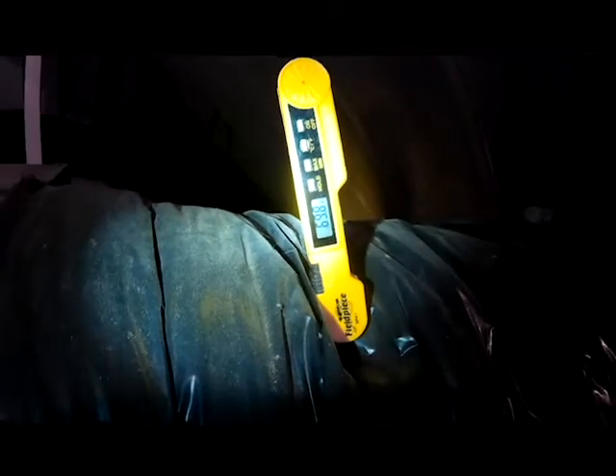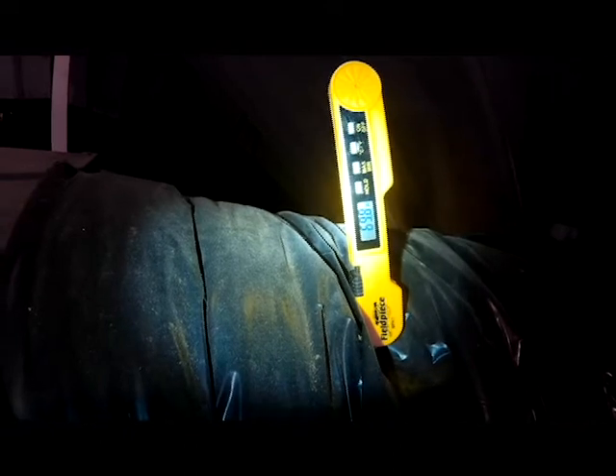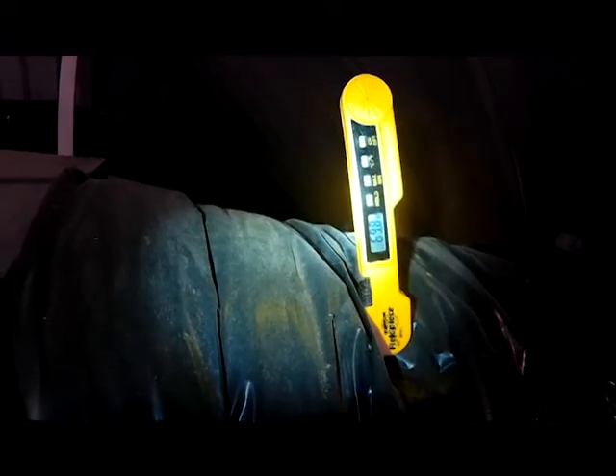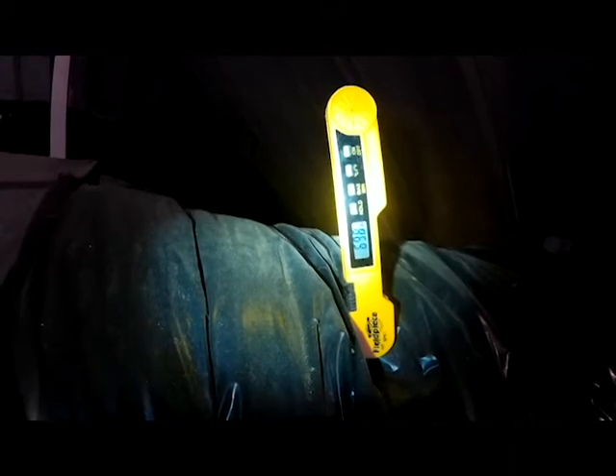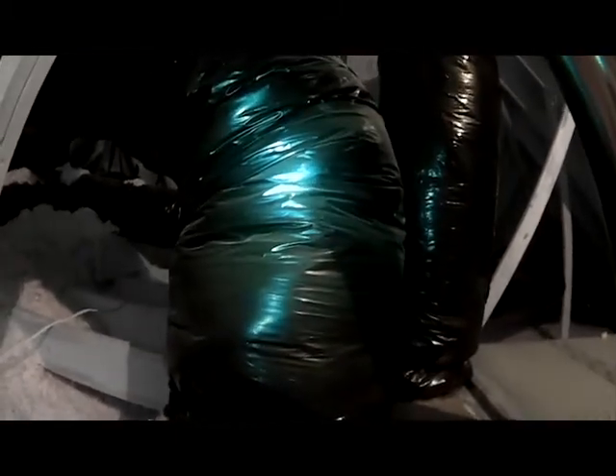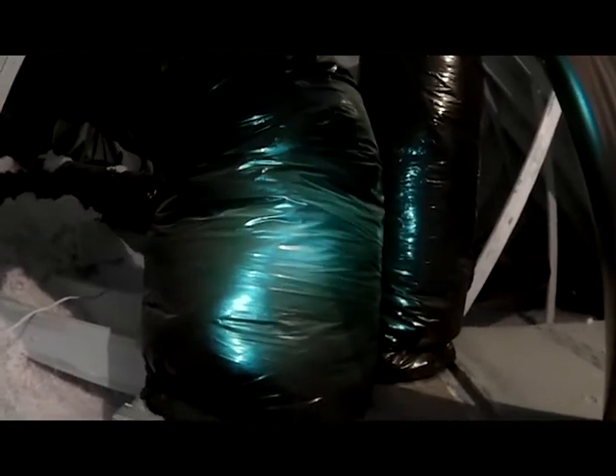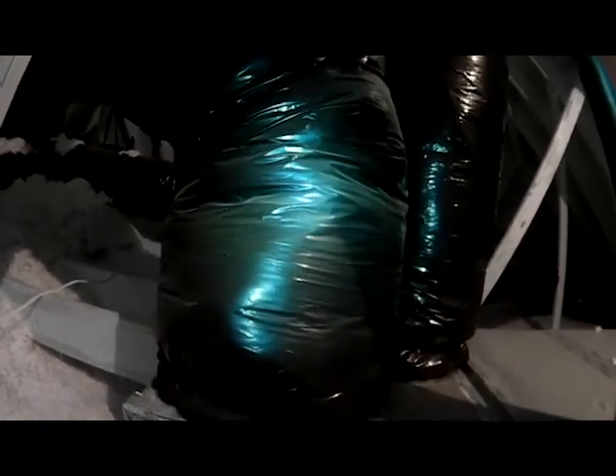All right, we waited for the temperature to stop rising, and it's basically saying our return temperature is 69, almost 70 degrees. So now we need to measure it on the supply. Now, we don't want to measure too close to our furnace. We want to take our reading probably about 3 feet down one of the ducts, so that there's no residual heat from the heat exchanger affecting our readings. So here's a big supply duct, and we're just going to put our temperature probe here.